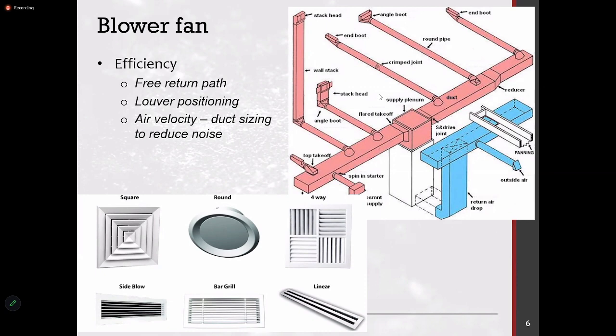And the other thing is louver positioning. If you have louvers installed at a very low level, that is also not very good because one thing is it could absorb the dust which is available on the floor, and there is also a tendency that somebody might push a cupboard or something like that and close the intake air, so that can block the total ventilation system. So that is about louver positioning.